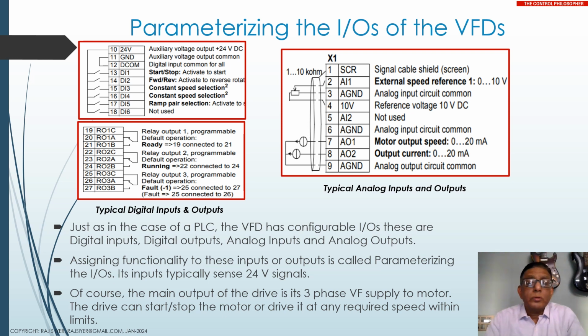Now we come to the parameterization of the I/O terminals of the VFD. Just like a PLC I/Os, a VFD will have multiple inputs and outputs: digital inputs, digital outputs, analog inputs, analog outputs. We have to assign a certain functionality, like one DI input can be used for start stop, or one can be an emergency stop, one a momentary start, one input can be used for braking, one can be used for DC injection stop, things like that.